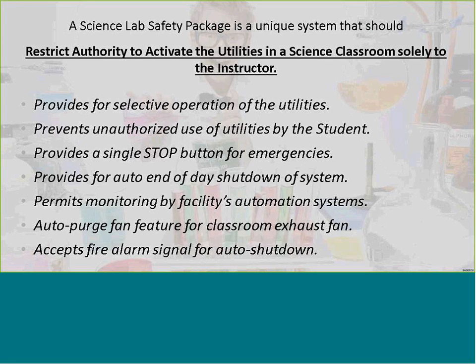And the other thing that you should be noticing is that we can tie into the fire alarm panel itself. The fire alarm panel will send a signal out, and that will disable the unit as well, so that we have complete shutdown during a fire situation. As long as that signal is maintained, you want to make sure that the system cannot be reset. So be careful how you set up your fire alarm signals there.